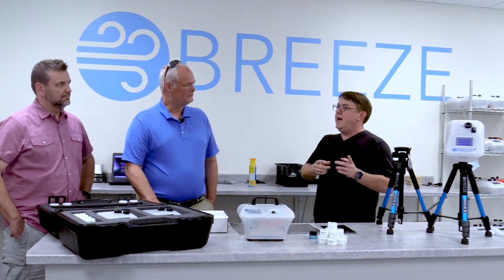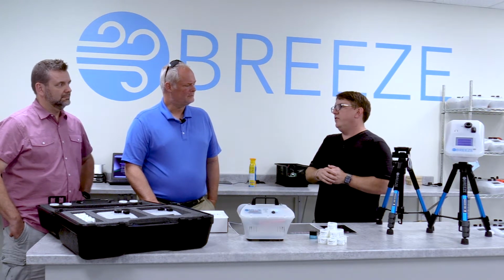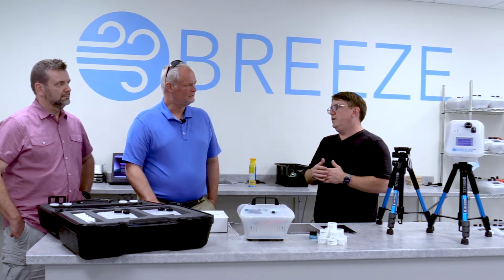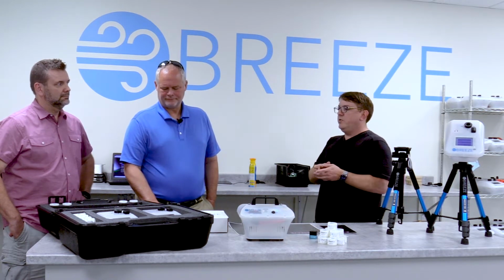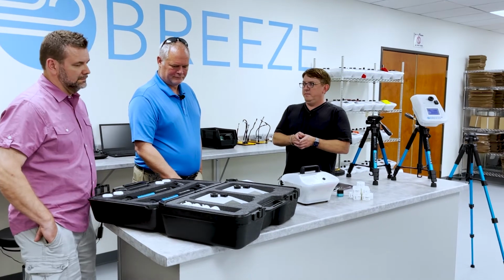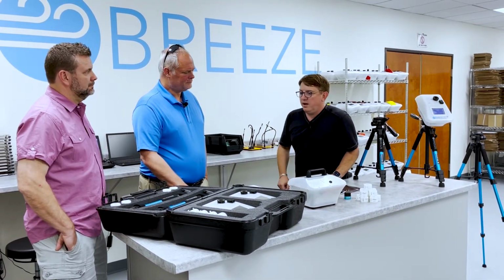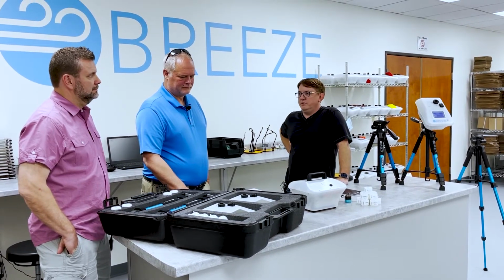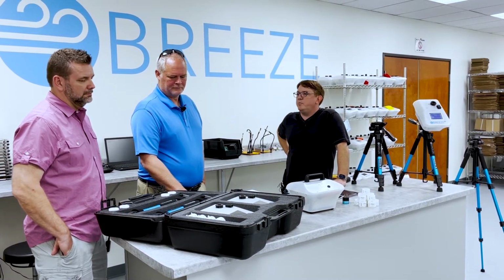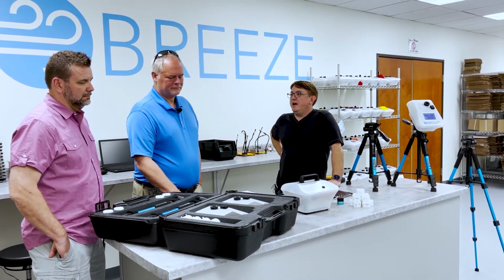By the time you get done with that, you're back outside, you're putting that one away, you're starting one on the other level. Most IAQ tests end up being 3 or 4, so you do this a couple of times. You're in and out of this process in 20 minutes, and you can pack a bunch into your day. Oh, and by the way, you have a secondary backup unit, so if one fails, your day isn't completely ruined. It's unlikely to happen. It's one of our products, but if it does, you have a backup.